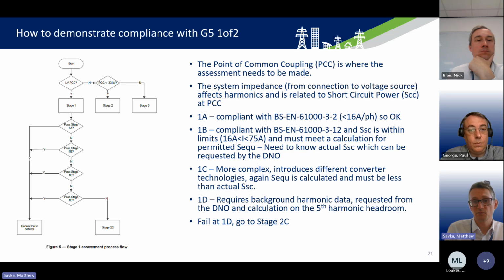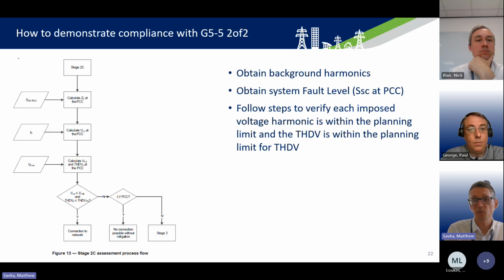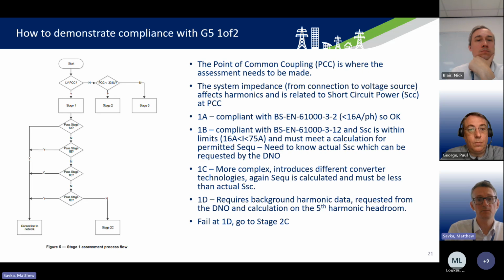If it doesn't meet those requirements, say it fails at 1B, you move on to 1C, which is slightly more complex. It introduces different converter technologies, and again the equipment power is calculated, and it must be less than the actual short circuit power of the site. Now, it's important to note that for 1C, 75 amps is about 50 kilowatts for three-phase. So if you've got single inverters that are 50 kilowatts plus, then you're straight in at 1C stage.